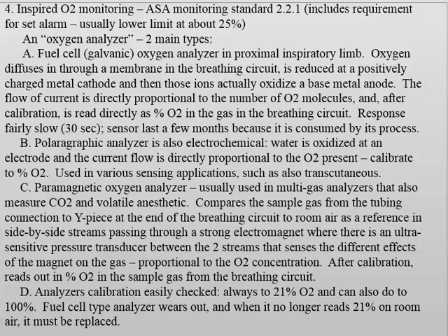It's possible that that could be an exam question to contrast that with the standard fuel cell one. I doubt that, but that would be a pretty deep question. But now at least you've heard about it. It's easy to calibrate. You usually check it to 21 and 100, and the fuel cell type, as it says, wears out and has to be changed out when it no longer reads 100.